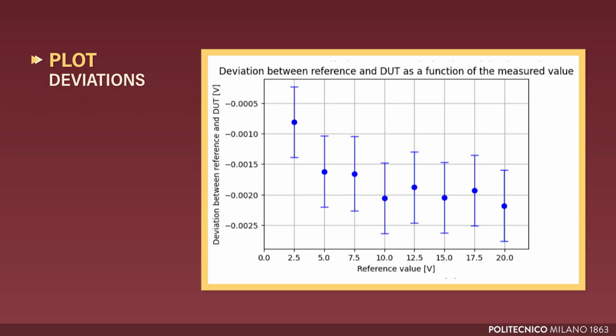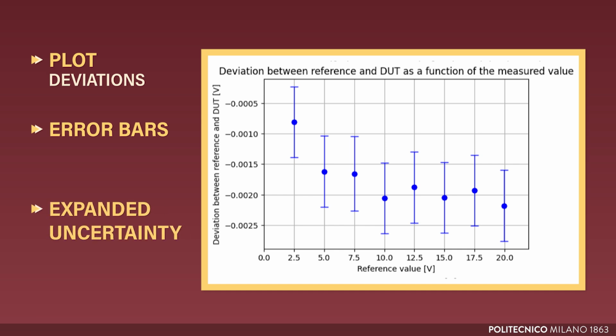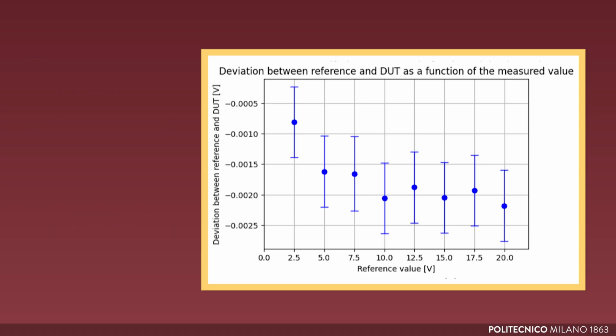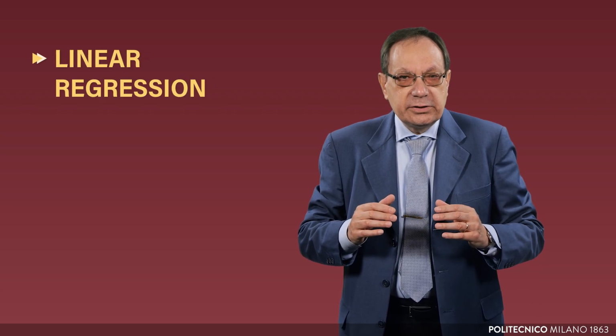These are the values in the second column of the table we saw earlier, which you can see in this graph, where the measured values are shown on the x-axis. On the same graph, you can also see for each point vertical error bars whose half-width is the expanded calibration uncertainty shown in the third column of the table we saw earlier. As you can see, we cannot say anything about what happens outside the measured values. However, by looking at the graph, we notice that the deviations follow an almost linear trend. This observation suggests calculating the line that best fits the deviations obtained.